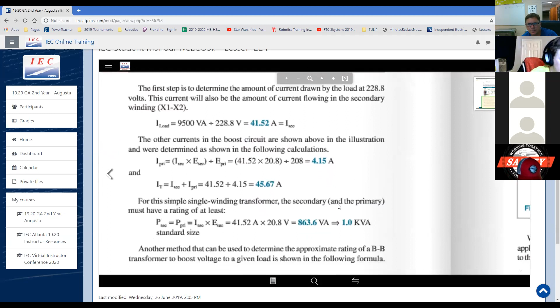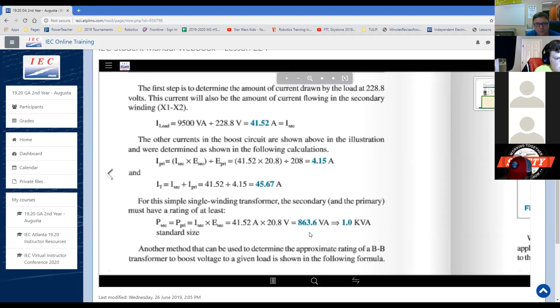So for the simple single winding transformer, the secondary and the primary must have a rating of at least - we need to find the power for the secondary, and the power of the primary. We need the current of the secondary times the voltage of the secondary. So 41.52 times 20.8 gives us 863.6 VA, which is close to 1 kVA.